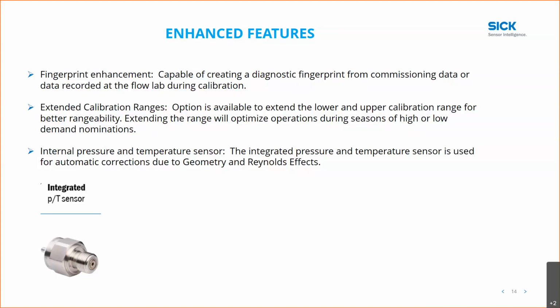So in other words, during the winter, you may have high demand, so you flow very high. During the summer, you may have very low demands. In the past, you've had to get a device that can measure the lower flow rates. By extending the lower calibration range, you might be able to do that with just one XT meter. And of course, the XT now has the internal pressure and temperature sensor. The integrated pressure and temperature sensor is used for automatic corrections due to geometry and Reynolds effects.